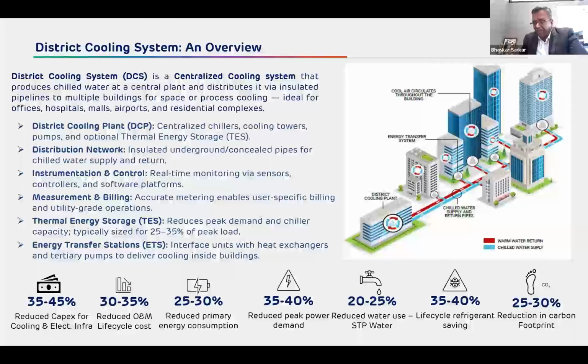And through consumption of that, what it also contributes is that if you see a building which has conventional air conditioning systems, the entire building is encapsulated by the heat which is generated by the air cooled outdoor units, and this heat raises the ambient temperature by 4 to 5 degrees across those buildings and in the entire township. And that enhanced heat again creates a vicious cycle, which means it has to consume more energy to combat that additional increase in the ambient temperature. Whereas if we use STP water for the cooling tower, the latent heat is absorbed and the water vapor is released into the atmosphere, so the heating effect does not happen. It also adds to the humidity of the atmosphere, unlike an air cooled system. So that is the benefit of using STP water and a water cooled system.